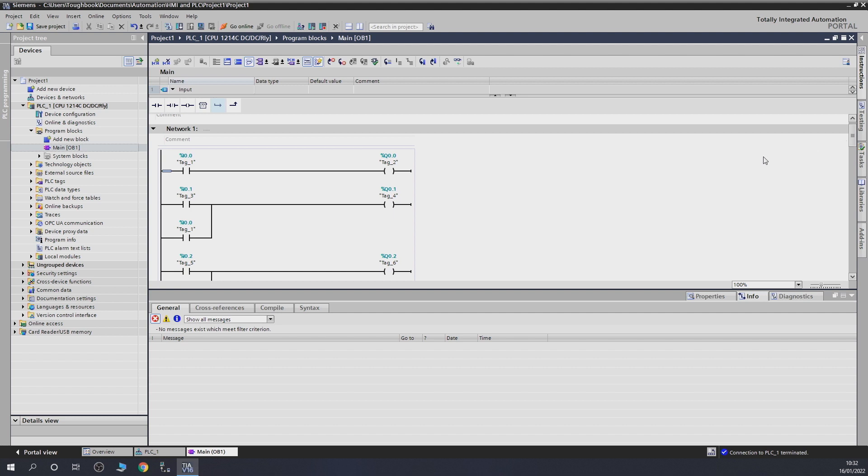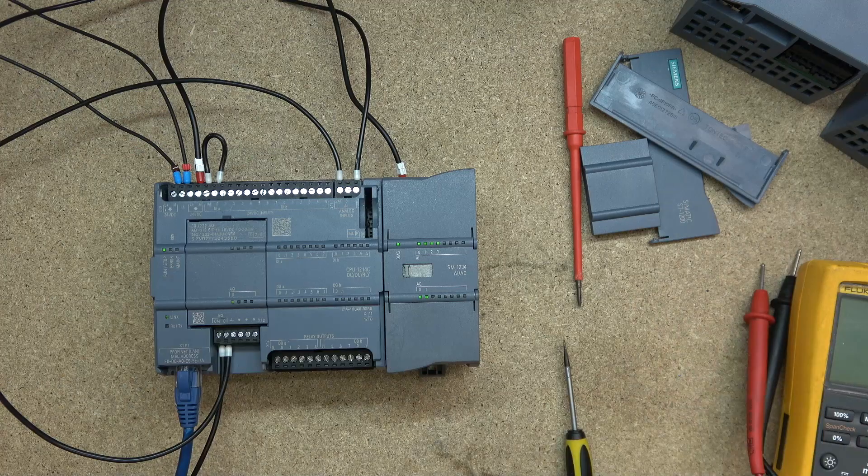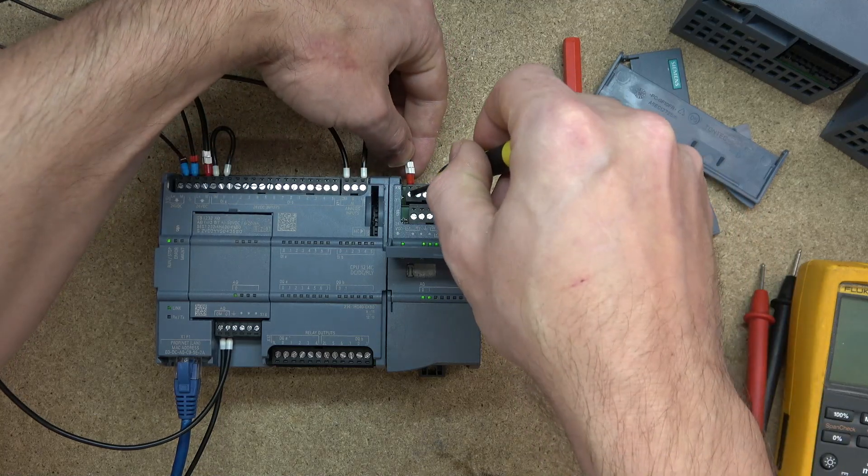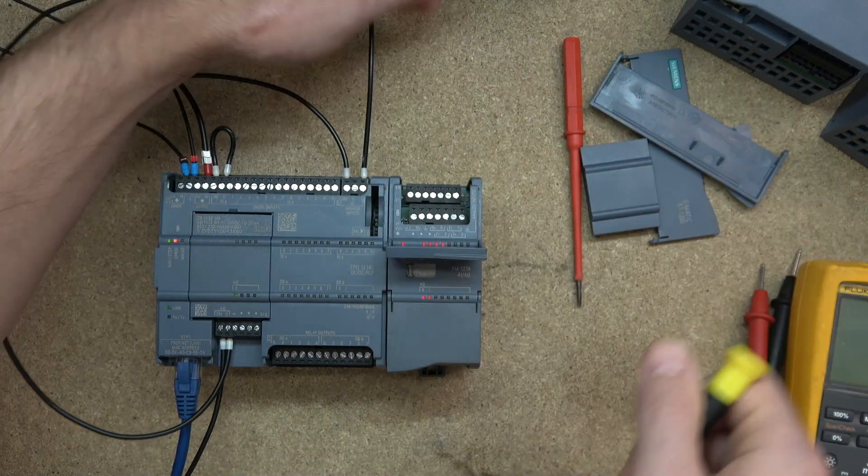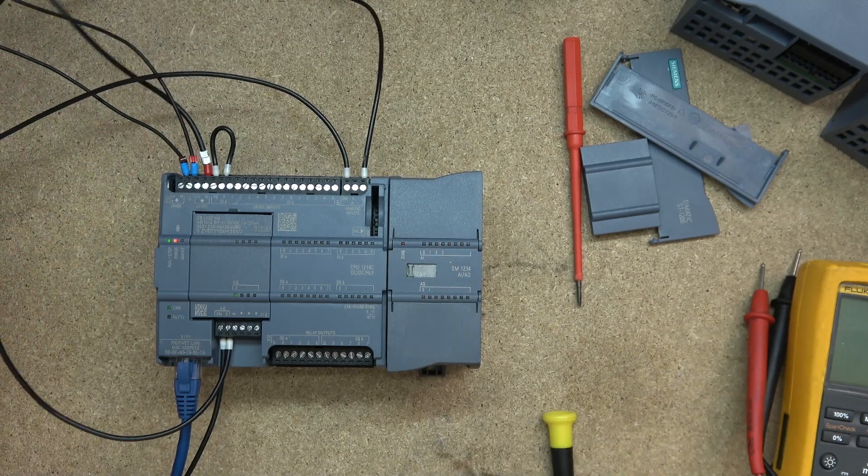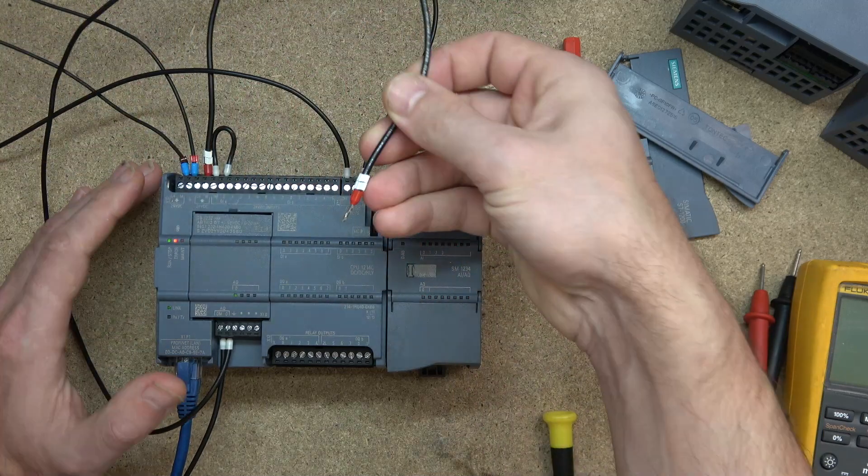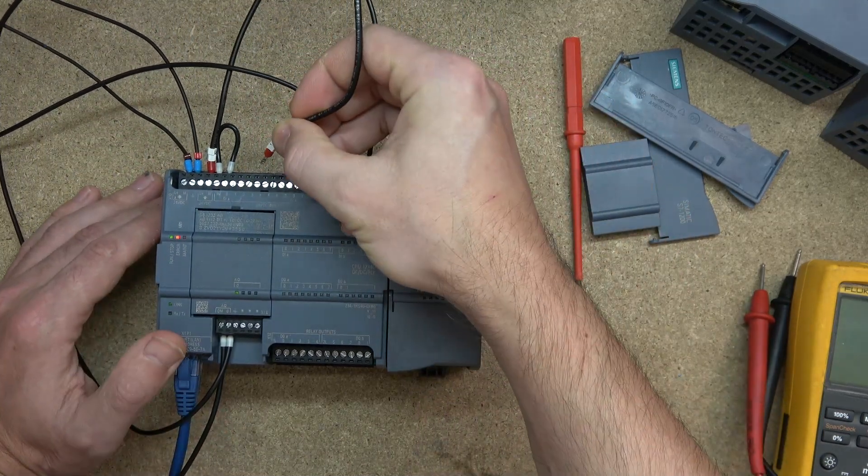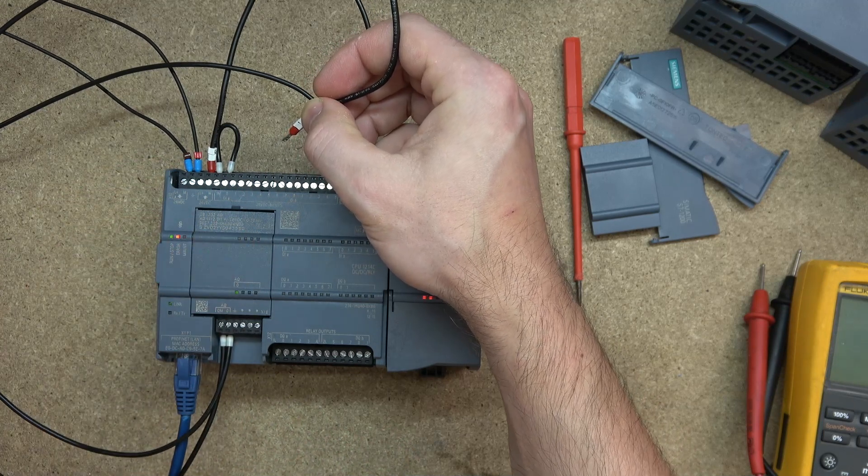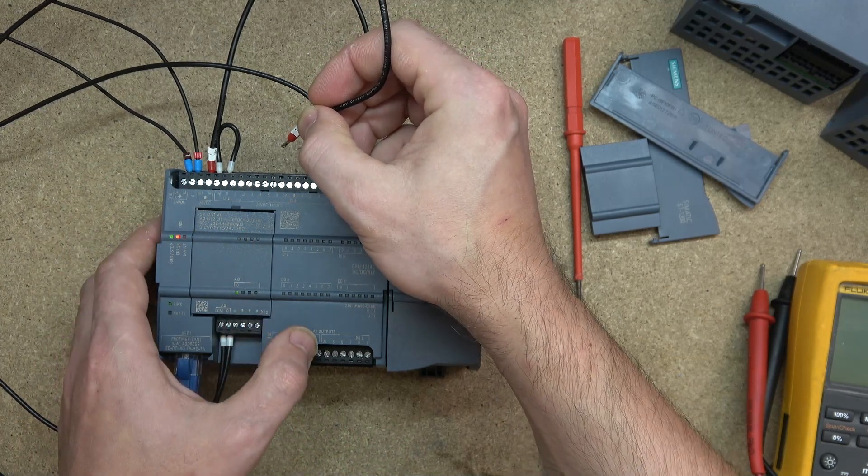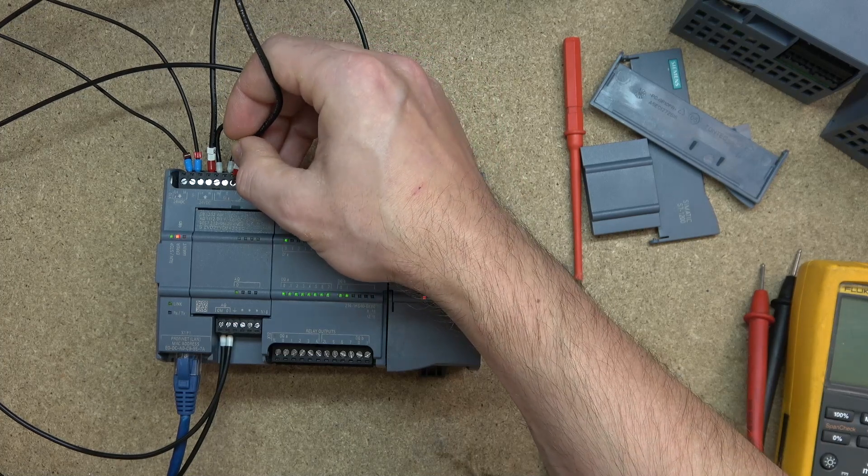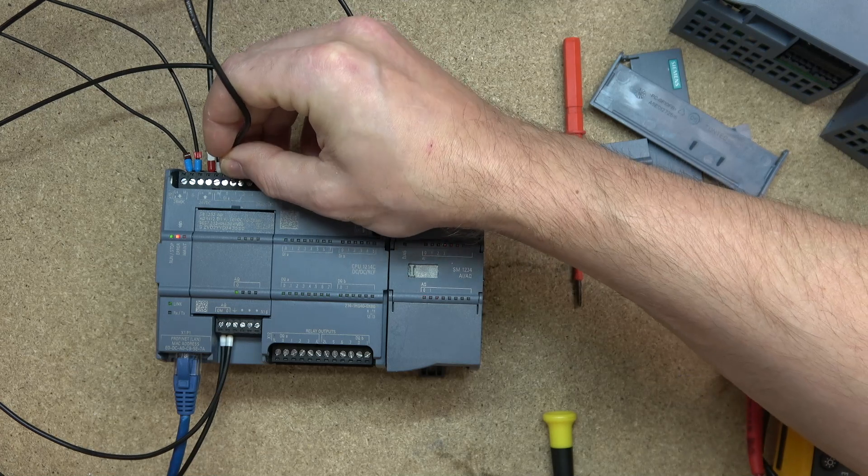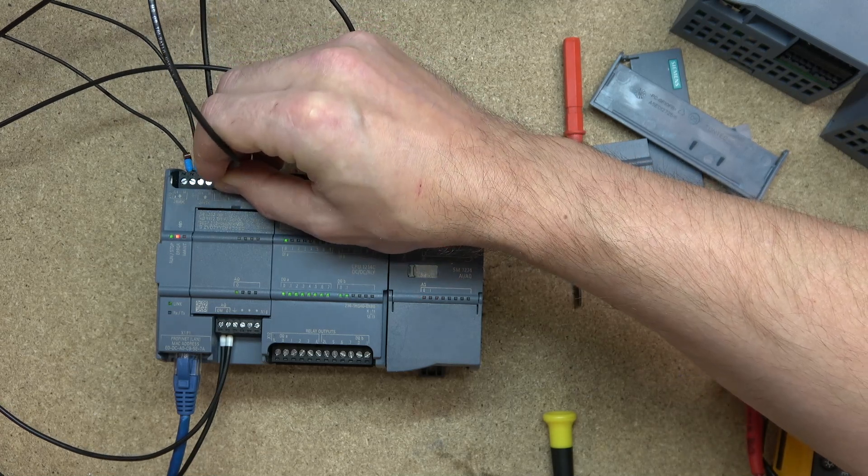So yeah, that's pretty much all we really need to do to determine that the controller is fully functioning. This controller was used. So IP address was set already. So let's first we're going to do, I'm going to remove this power cable from here. So as you can see, that one starts flashing. That's for diagnostics purposes to tell you that the power is missing from the card. So what I'm going to do, I'm going to take this cable in here, quickly run through my inputs and making sure they're activating and not just activating, also being recognized within the program, which will tell me if the outputs are coming on.